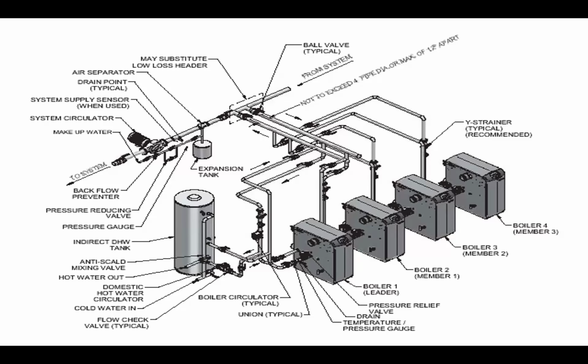As you get out into the distribution main, very simple, very subtle little drawing, air separators. Hottest point in the system, we're releasing air bubbles from the fluid, from water. We want to have some type of air separating device to prevent air from being a problem. We're going to have an expansion tank. It's a very simple little drawing in this picture here, but expansion tanks play a huge, very important role. Kind of subtle, sits off to the side. Incredibly important that it's installed correctly, that it's sized properly, and located properly. So we'll get into that.